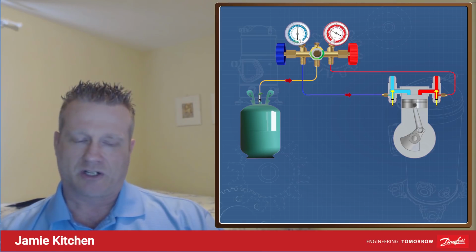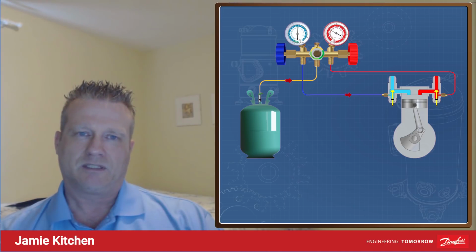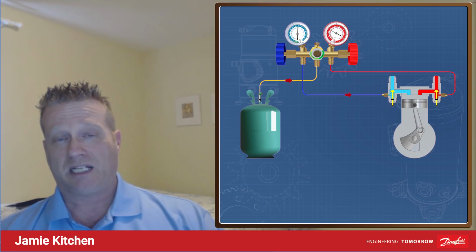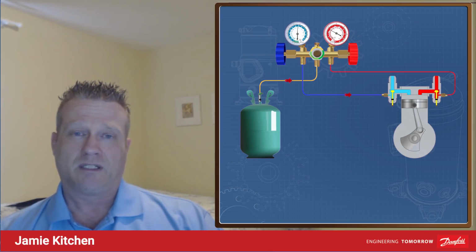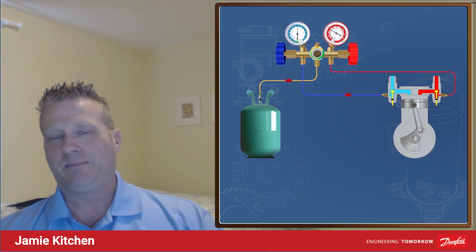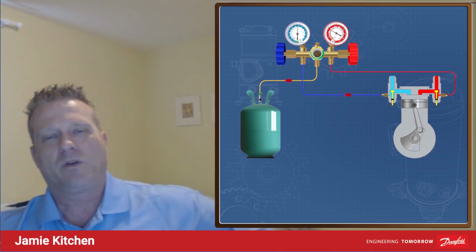And when that compressor starts and the sump pressure drops, that oil is going to foam. You're going to lose lubrication. Okay? And don't kid yourself. People think scrolls are liquid proof. Yeah, a scroll will take a liquid slug. That's great. But that lasts seconds. All right? They still got bearings. They still need to be lubricated, especially that upper bearing right below the scroll.